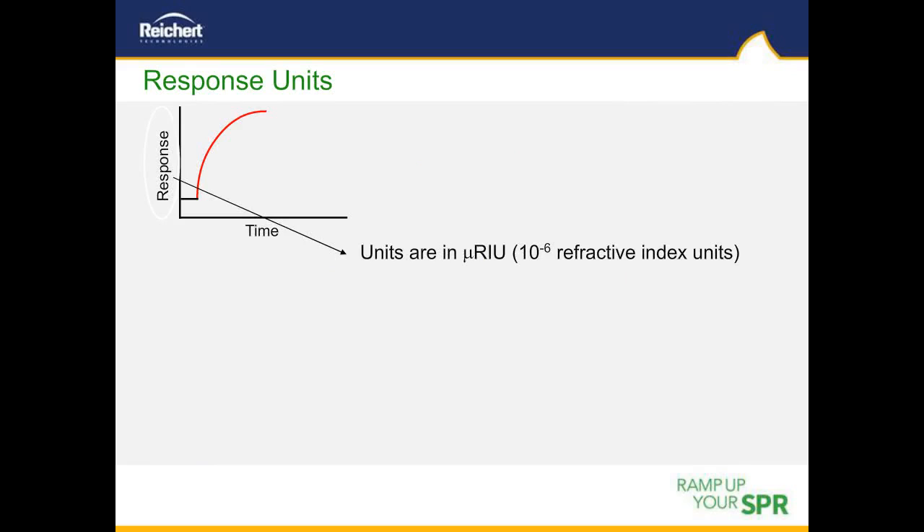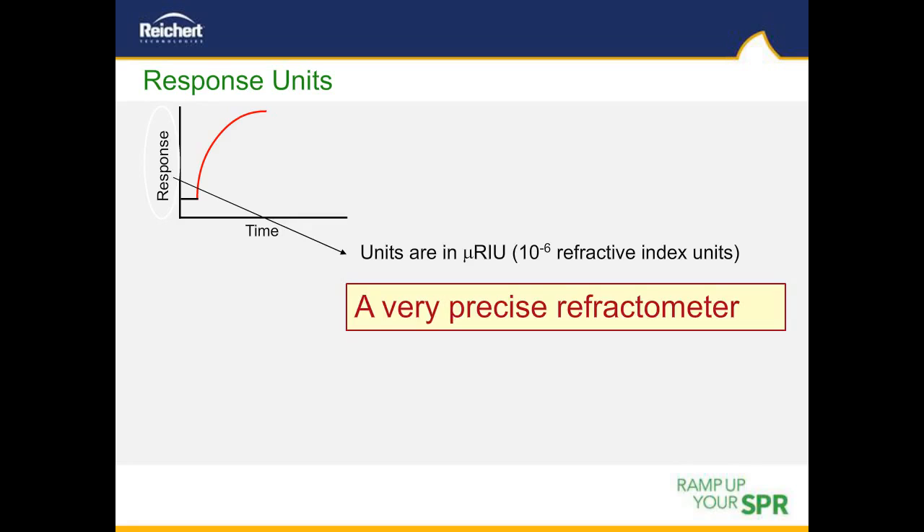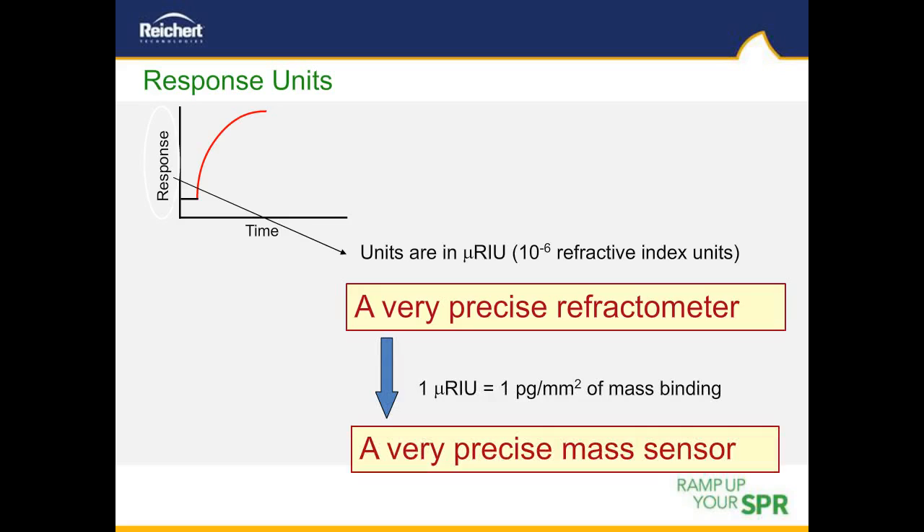SPR instruments measure very precise changes in refractive index or mass at the surface of the sensor chip. The traditional unit of measure is micro refractive index units (µRIU), or 1×10⁻⁶ refractive index units, which corresponds to a change in mass of one picogram per millimeter squared. In essence, SPR is a very precise refractometer and mass sensor. The RMS noise level of Reichert systems is about 0.05 µRIU, equivalent to a mass change of 50 femtograms, enabling monitoring of very low molecular weight molecules or very few molecules of higher molecular weights.